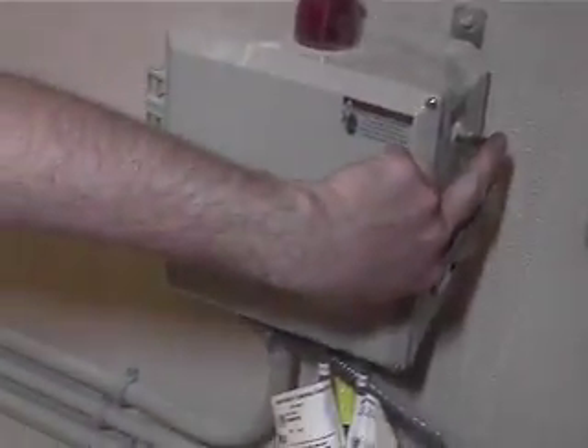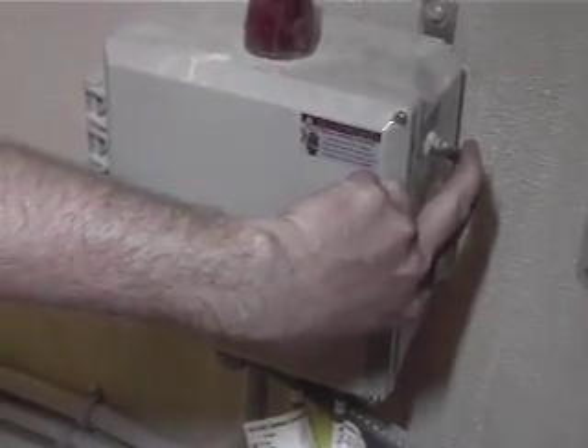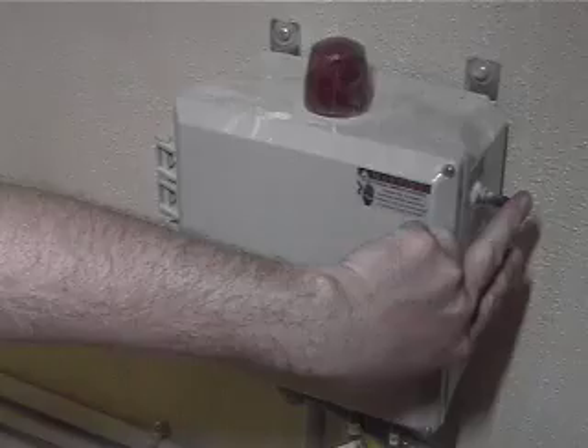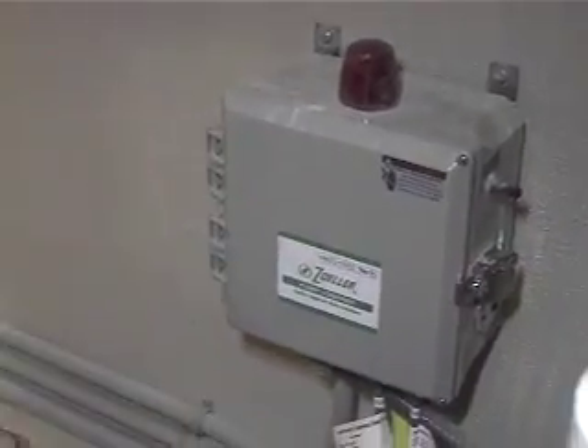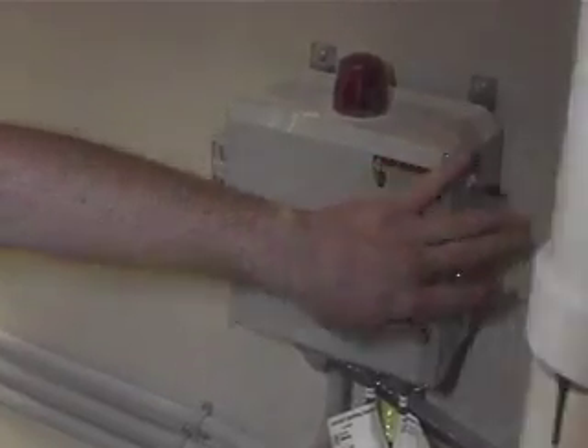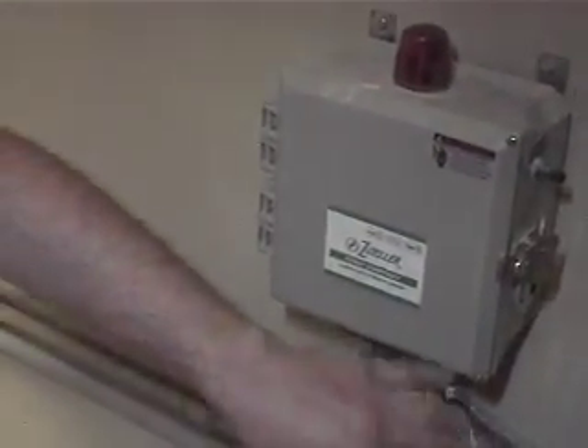If the pump did not start and the water level gets to this float, that float will lift up and it will set off an alarm on this control panel. And I will demonstrate that for you. There is a test button here that I'm just going to simulate if it were to go into an alarm. That's what you'd be getting. You're going to hear it, and you're going to see it. If you do need to silence it, just so you can get that noise to stop, you'll just pull the switch towards you. It'll silence that alarm.